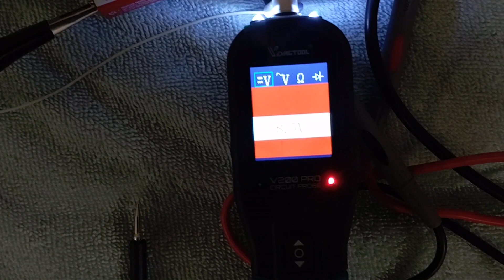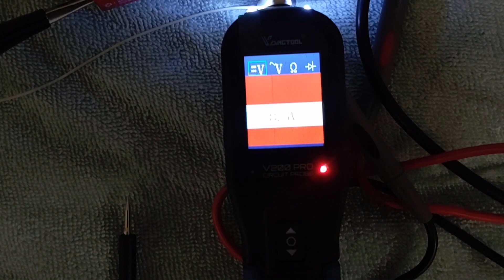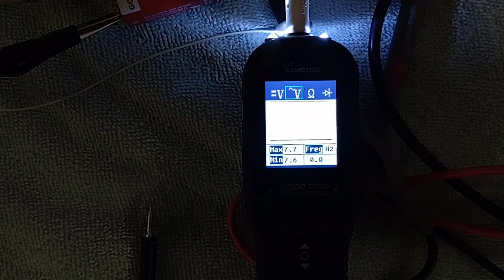We measure the same defective battery on a meter with low but not very low impedance. We have lower volt readings. This meter will read DC voltage on the AC volt scale, which is unusual and useful sometimes.